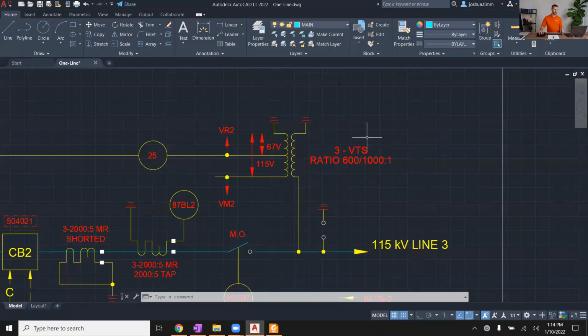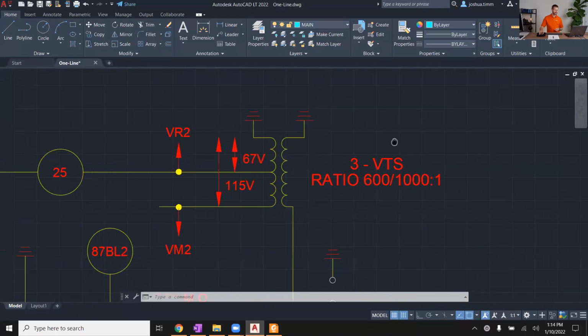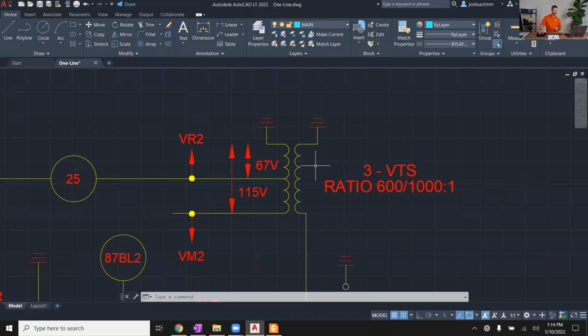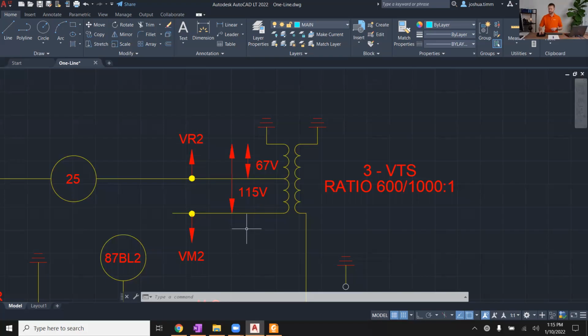Let's actually look at a real life PT here in a one line drawing. This is the primary side. This is the secondary side. And you notice there's a 67 volt tap and 115 volt tap. And it shows two different PT ratios or VT ratios here. Which ratio goes to which? Somebody tell me the 67 volt tap, which PT ratio should we use for that case? 1000 goes to 67, and then 600 goes to the other one. The 115, exactly. Good job, Hussein. So smaller tap, larger PT ratio. Larger tap, smaller PT ratio.